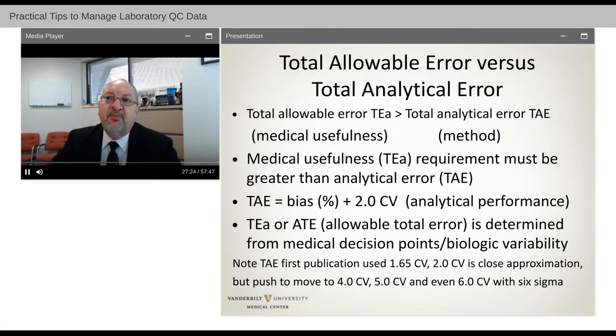Now, defining total allowable error versus total analytical error. Our total allowable error is the medical utility, the biologic variation of that analyte, glucose, sodium. The total analytical error is our method error, so TAE versus TEA. Now, medical usefulness should be wider and must be greater than the analytical performance of our method. Otherwise, the test is not meeting patient care needs. In other words, our total analytical error is our bias and two times our standard deviation or our coefficient of variation. Now, our total allowable error is determined from medical decision points and biologic variability.